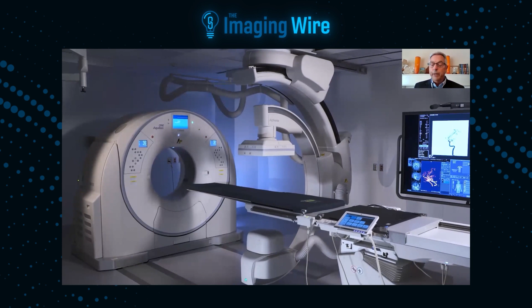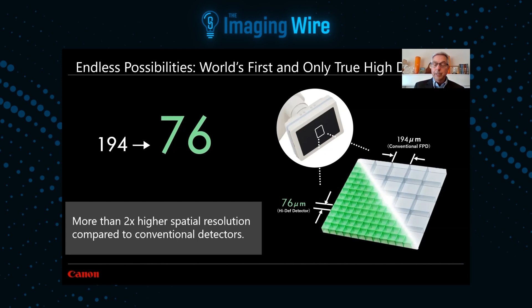We have this high def imaging that I mentioned earlier. A lot of folks have asked, okay, what the heck does that mean? What it means, and we call it HD76, by the way, is that it's actually a second detector that's built inside of the actual flat panel detector, the angio flat panel detector. So you have a piece inside of that that's at 76 microns. That's where we get the 76 in HD76. And what it allows you to do is it more than doubles the resolution of the image.